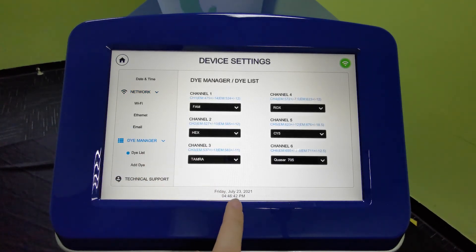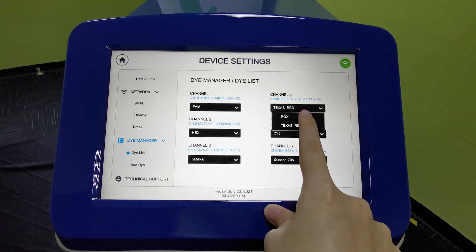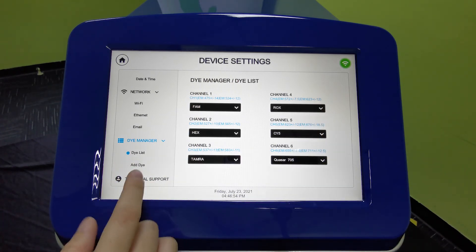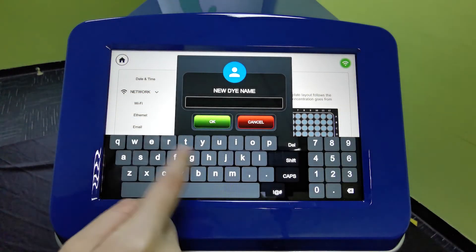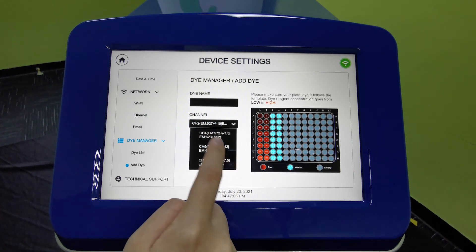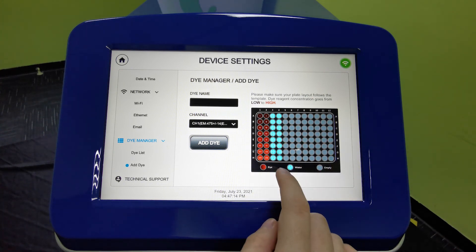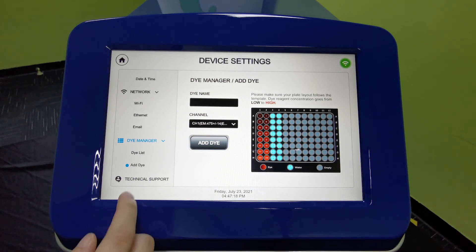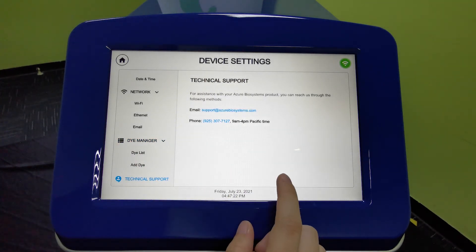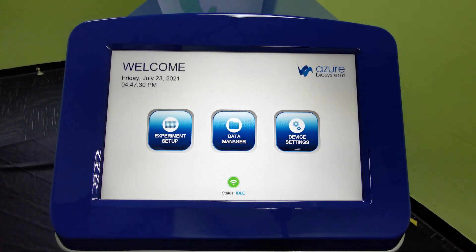Under Dye Manager, this is the dye list shown earlier when setting up your protocol. You can change the name of a dye in a given channel. If you have a custom dye, click Add Dye, enter the dye name, and select the channel it will use from the preset channels. This is a guide for testing your custom dye — you can also find this in the user manual. For technical support, you can email support at azurebiosystems.com, or contact your local support from ExoScientific in Singapore. This concludes our demo session — thank you.